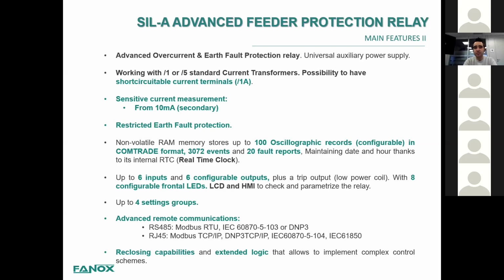Another important issue is that we have reclosing capabilities, and we have an extended logic that allows to implement complex control schemes, as we have done in the past with some of our clients, and for more complex situations in combination with other devices that can be installed in the park and give information to this relay, and this relay makes these complex control schemes.